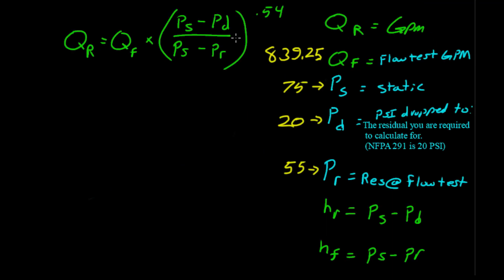So, first off, we'll work this through one time to see if we're getting the same answer on this equation and the next one. So, to go ahead and rewrite this equation, we will go QR equals QF. Our gallons per minute was 839.25 times, put our parentheses there, PS. So, our static pressure was 75 minus our desired drop 2 pressure, 20 PSI, divided by. It's a fractional line. It means divide by.